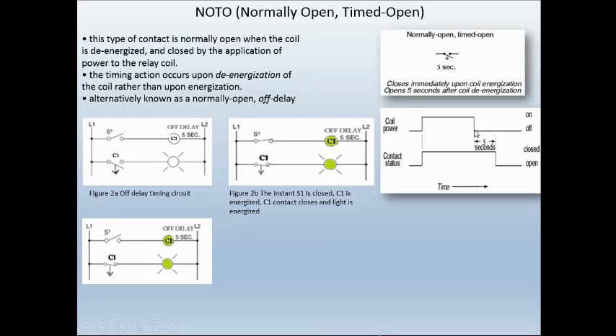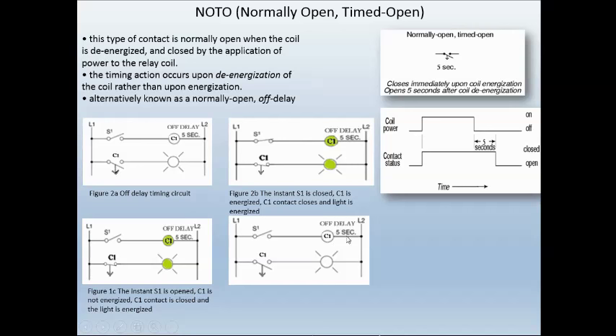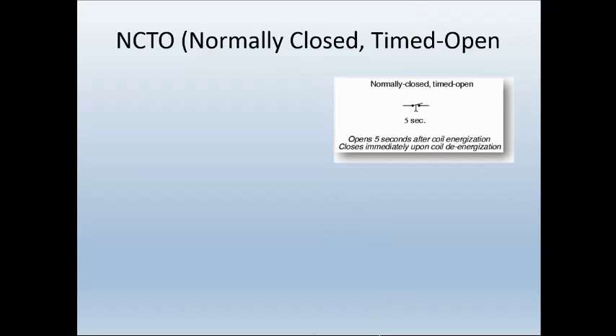When we open S1 and the coil becomes de-energized, the timer starts counting. You can see the coil power went to off and the timing sequence begins. It stays closed until five seconds have completed, then that contact drops open and the light shuts off. So with our normally open timed open: the coil becomes energized and the contact closes right away. But when the coil becomes de-energized, the counting begins for five seconds and then the contact opens up.